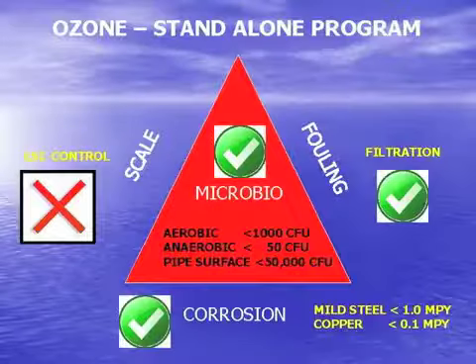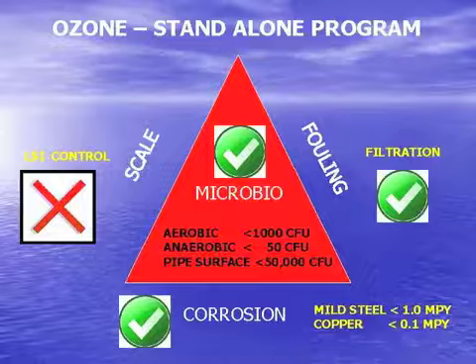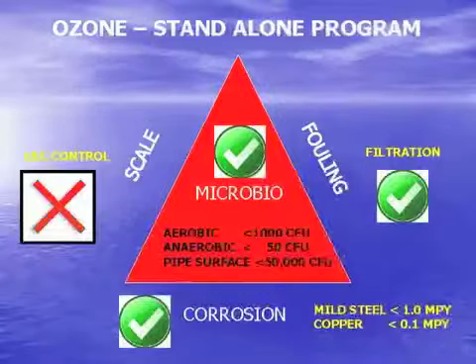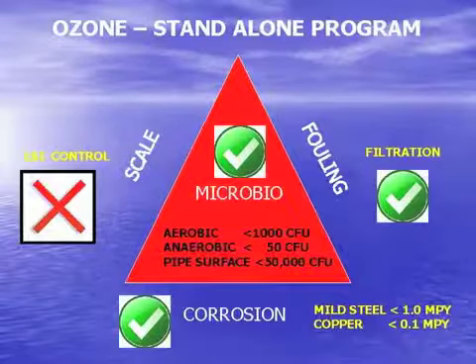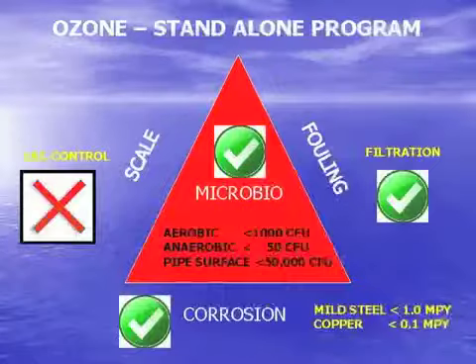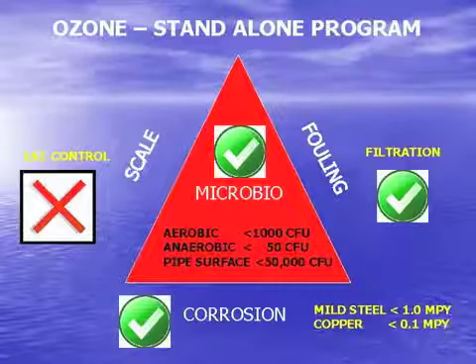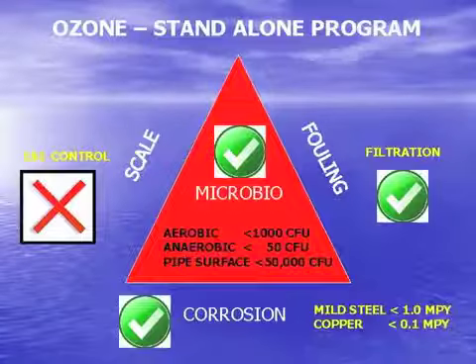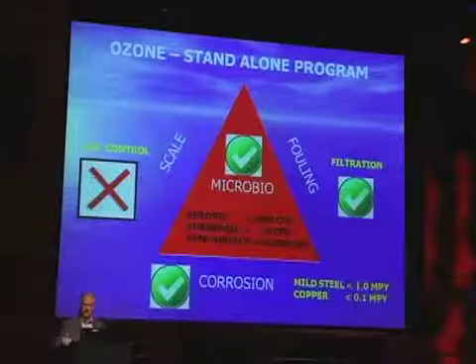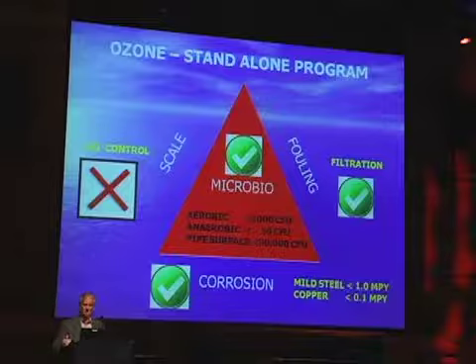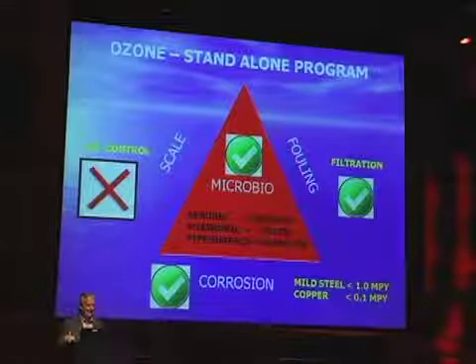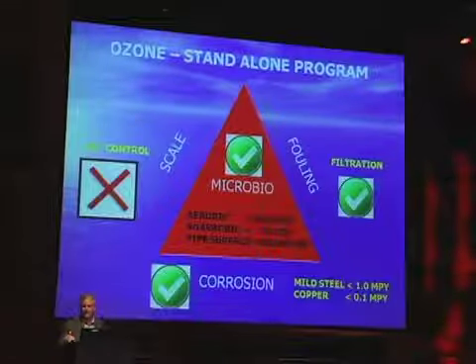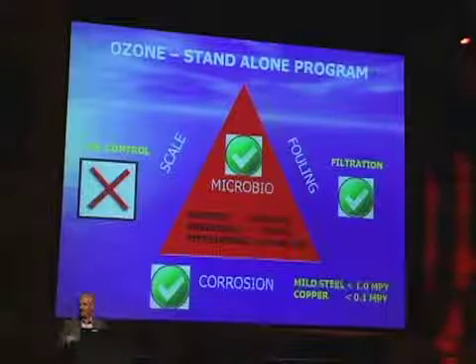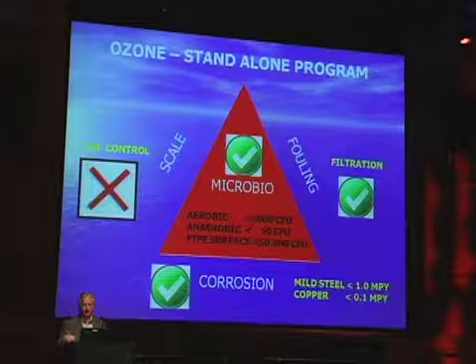When you look at ozone, about 10 years ago it made a run where people said we can just put ozone in the water and it'll solve all your problems. It actually did fairly well, to be honest. Ozone by itself is basically oxygen on steroids. They take oxygen, run it through an arc process, and bring it up to the O3 state. It's a nicely smelling molecule - if you're in a lightning storm and smell that sweet smell, that's basically ozone. It doesn't want to be there; it wants to go back to O2.